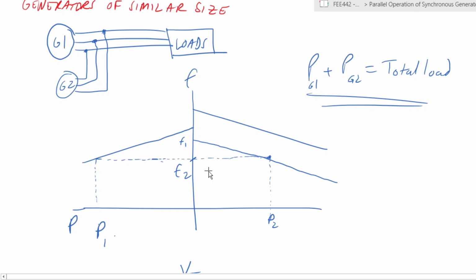So what do we do? Yeah, you want your frequency being constant, but you want to change. You want P1 to produce less, say, you want it to come here, say P1A, right? So let's see how that would look like and what we would have to do to achieve that. Okay, so what we want is we want to retain them at the same frequency, but you change the value of power being supplied. So this means that you would then have to change both set points.